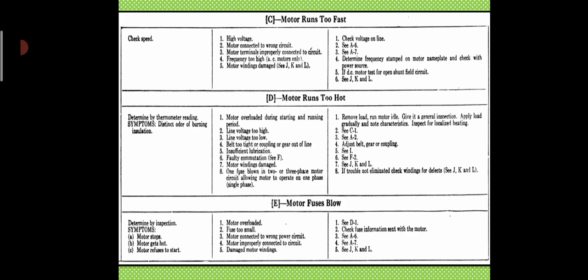Now, motor runs too fast. Check speed. The causes are high voltage, motor connected to the wrong circuit, motor terminals improperly connected to the circuit, frequency too high, and motor windings damaged. The remedies are: check voltage on line, determine frequency stamped on motor nameplate and check it with the power source. If it is a DC motor, test for open shunt field circuits.